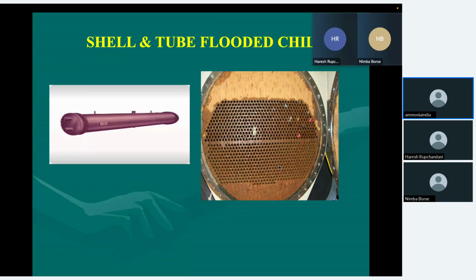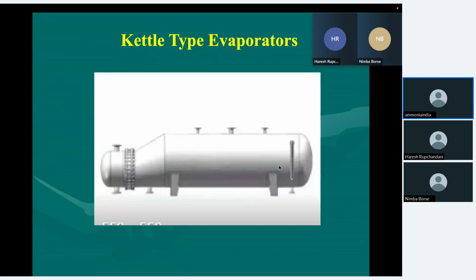I came across one design, a chemical manufacturer's kettle type evaporator in a Gujarat plant, in a Baroda petrochemical plant. And they said, we are going to manufacture heat exchangers. You don't provide us the heat exchangers. And he used this kettle type heat exchanger as per their chemical engineering design. The chemical design or kettle type design has the tubes right up to the top of the vessel. A little bit of gap is left, as you can see in this vessel. With the result, whenever they started the plant, the liquid used to come to the compressor.